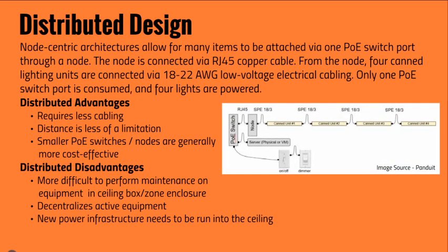Now let us understand the decentralized architecture. I call it a node-centric architecture, which allows for many items to be connected via one PoE switch port through a node. The node is connected via RJ45 copper cable. From the node, four lighting units are connected via 18 or 22 AWG low voltage electrical cabling. Only one PoE switch port is consumed and four lights are powered on. This is a very cost effective design and is used in small and mid segment enterprises.